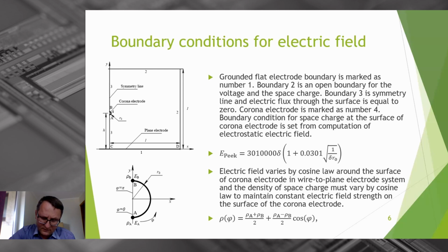It is checked whether the electric field exceeds the maximum field strength value determined by Peek's law. If true, the space charge density is increased by a small value at that point for the next iteration. If the electric field strength becomes smaller than Peek's value, the space charge density is reduced at that point by a small value. Corona discharge always starts at point A.